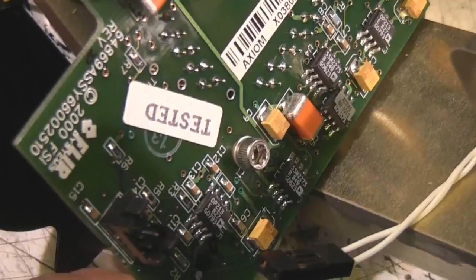Not a great deal on the actual image sensor board. It looks like the sensor, or at least these gold coloured pins, are soldered straight to the board. This whole sealing thing, my best guess is that it's a vacuum and the sensor itself is suspended in a vacuum to minimise any thermal leakage into and out of it, because you're trying to build a thermal image on the surface, and you don't want any ambient affecting it, but also you want the thermal mass to be very low.